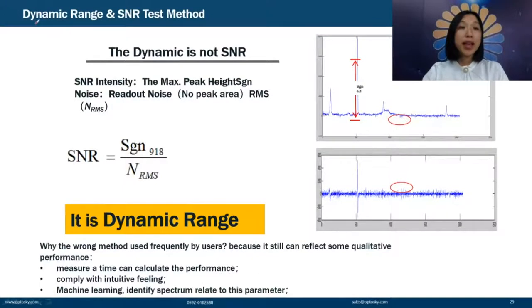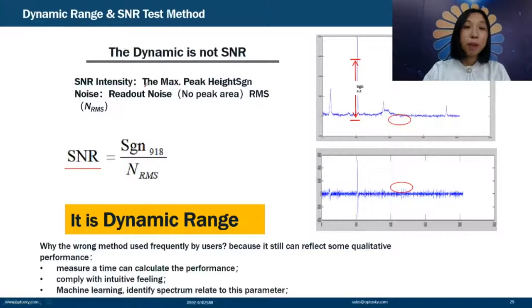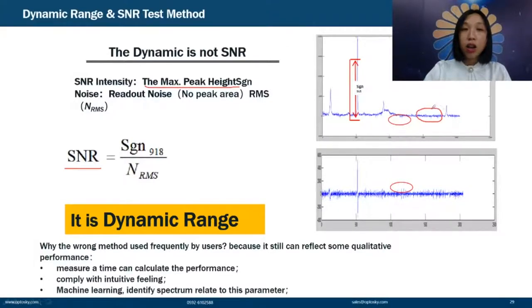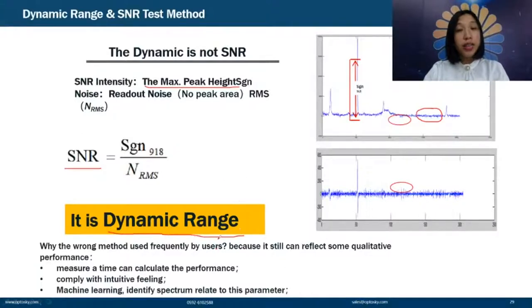After resolution, we must distinguish dynamic range from signal-to-noise ratio, as many people confuse them. Customers often calculate SNR as: maximum peak height (e.g., at 918 nm) divided by the RMS noise. Actually, this is the dynamic range formula, not the true SNR formula. However, customers still use it frequently because it is easy to measure — just one spectrum acquisition — and it aligns with human intuition: if noise is large the value is small; if the peak is high the value is large.